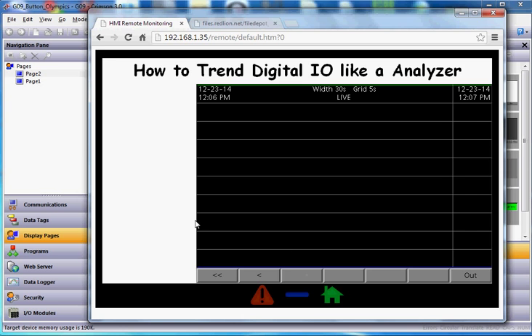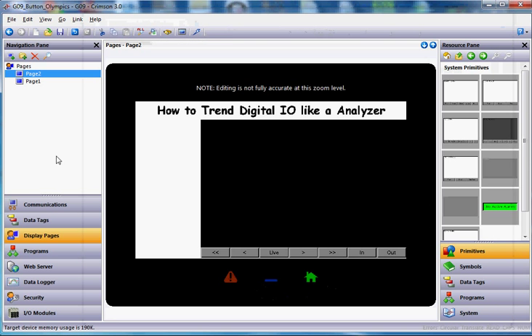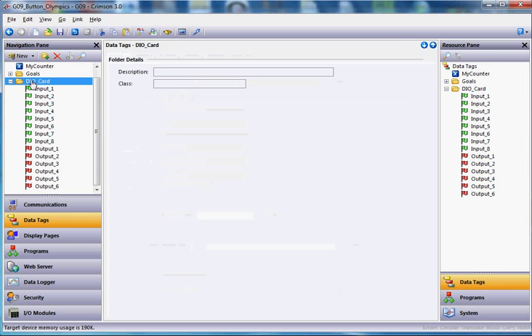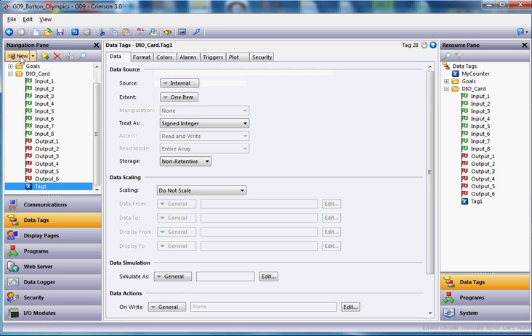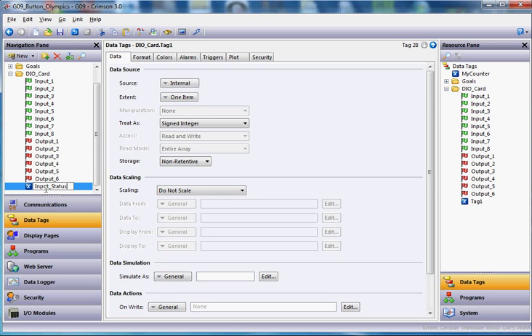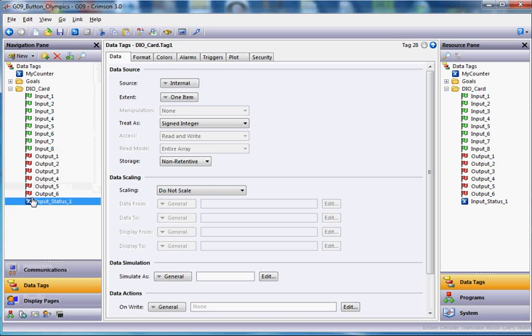So to make that happen, I'm going to go back to data tags. So I'll go to the left side, go to data tags on the left side. And I'm going to, in this example, I'll click here on the folder. I'm going to create a numeric tag. These are all flag tags because this is a discrete, which is correct. But in this case, I'm going to click the new button here by default. And I'm going to get a blue X, which is a numeric tag. And I'm going to call this one input underscore status underscore one. And what I'm going to do is I'm going to make this tag here equal to this one. Watch this trick. Notice currently it's blue. The X is blue here because at this juncture, I don't have a map to anything. It's currently set to internal.